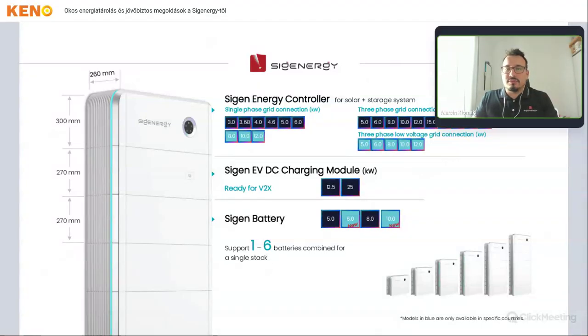A 10 kilowatt hour battery is not generally fully 10 kilowatt hours, it's 9 batteries, each having around 1 kilowatt hour of usable capacity. In the data sheet it's very clearly stated how much; it's purely for marketing purposes that this number is used. Please check it carefully once implementing the product to the customer.